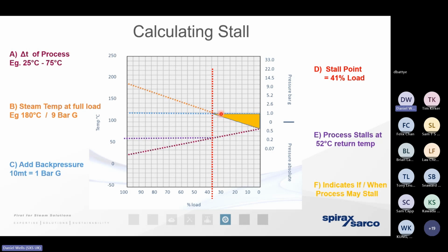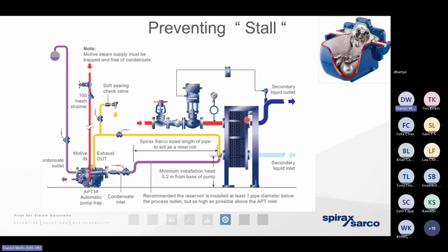Because when the process occurs in this area, a steam trap is not going to be suitable. Well, that's when we can move towards what we call an automatic pump trap. It's basically the big brother of a float trap. A float trap needs a differential pressure across it. When we don't have that differential pressure, the float trap will flood. It will operate a little mechanism within the body of the pump, and it will call for an input of high pressure steam that exists ahead of the pressure reducing valve or control valve. We're borrowing a very small amount of high pressure steam for motive energy purposes to shunt the condensate away.